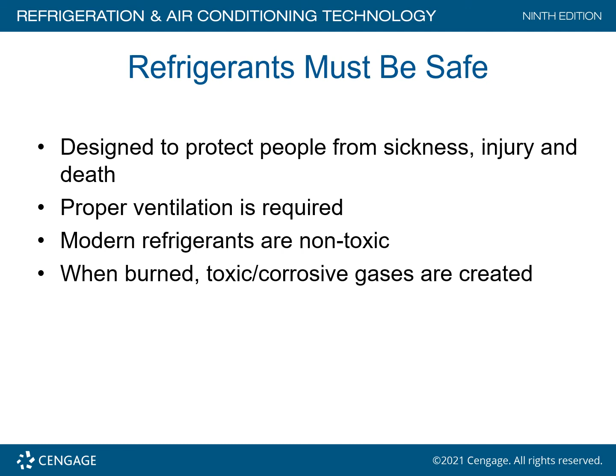Refrigerants must be detectable. Methods used for detecting leaks include soap bubble solution, which pinpoints leaks and works well most of the time. I use Simple Green because it's a little bit cheaper, and you can also use ordinary liquid soap and dilute it. The halide leak detector uses an open flame.